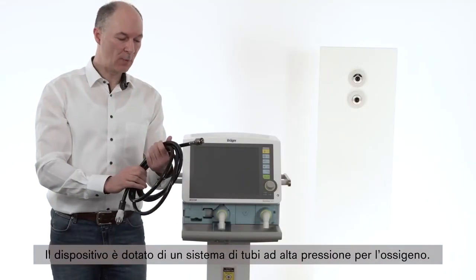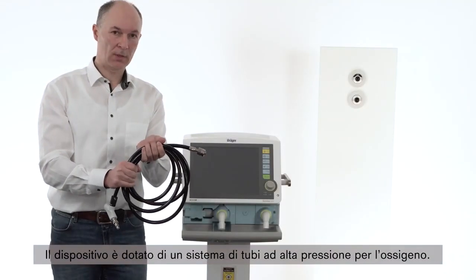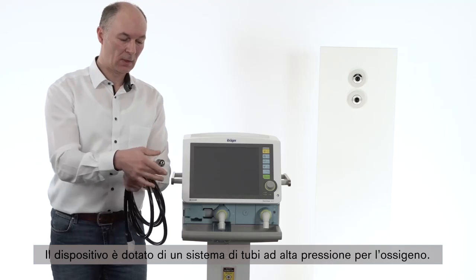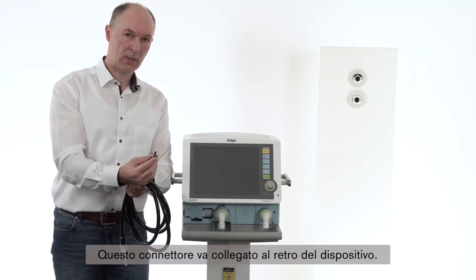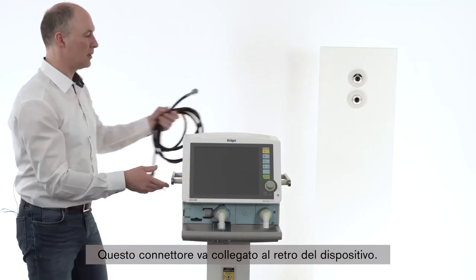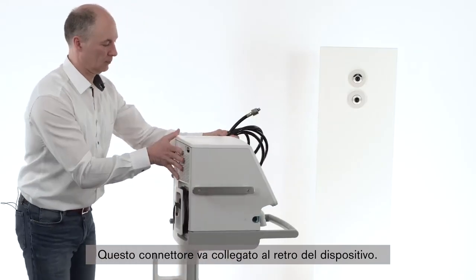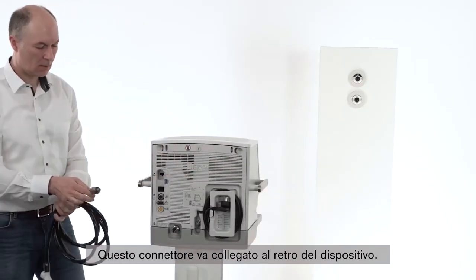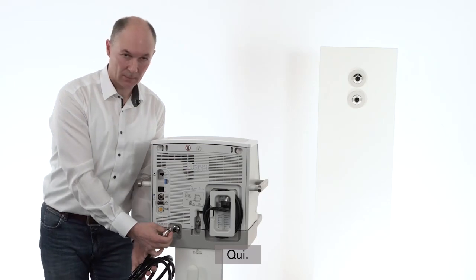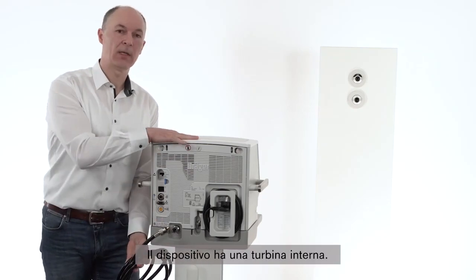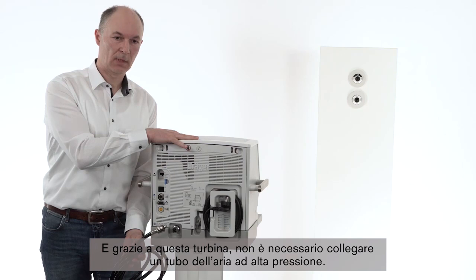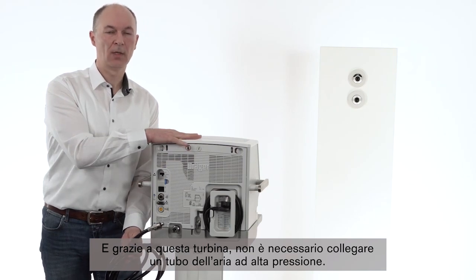The device comes with a high pressure hose system for oxygen. This connector you have to attach on the back of the device, which is located here. The device has a turbine inside, and because the device has a turbine, you don't need to attach high pressure air.